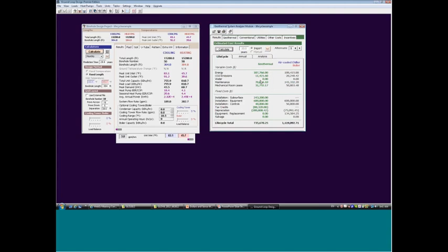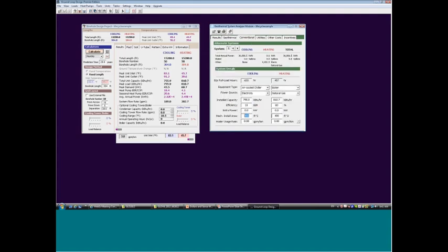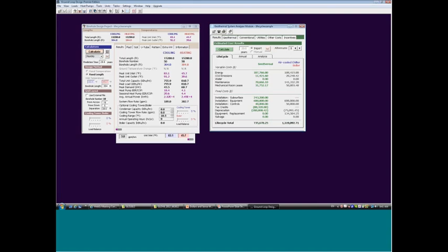Maintenance costs are about halved. My mechanical room lease value, remember we said the geothermal system is going to have about 500 square feet of space being built or consumed. Conventional is having 800. So what's the value of that? We put that at about $31,000 cost for the geothermal space and about $50,000 for the conventional space. So you're saving on this line about $20,000 for the geo system.